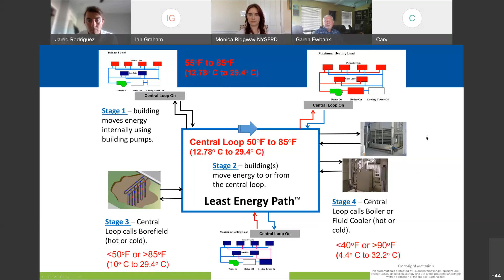In the built environment, we have cooling towers and boilers that we don't have to use all the time. If we look at temperature bands, there's a lot of times we do not need those running. And so when we get our loop temperatures a little bit further out of range, we'll simply bring in those devices to again modify that loop temperature. And so that reuses a lot of the equipment that you may have out there with no additional cost. Next slide, Carrie.